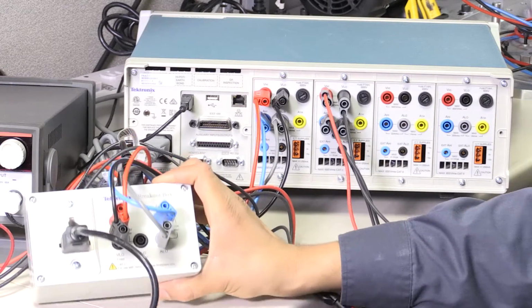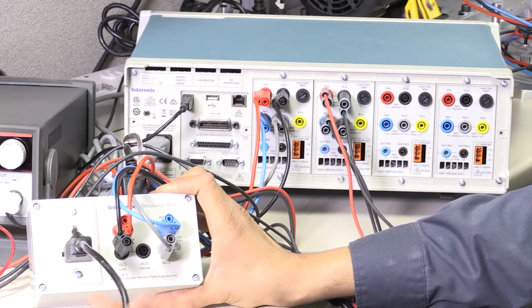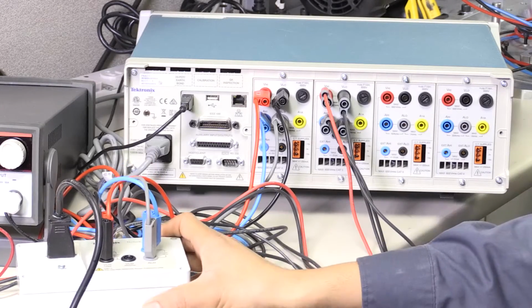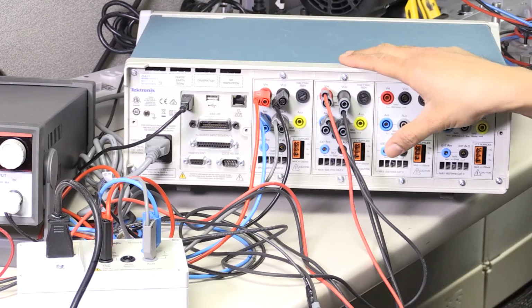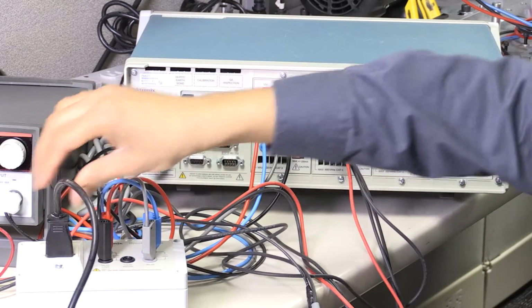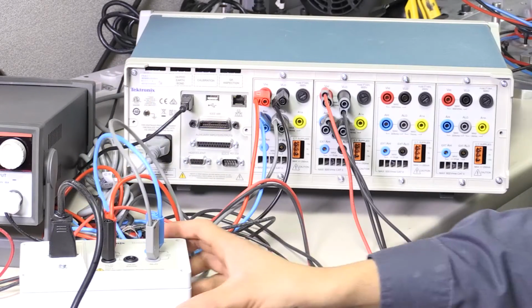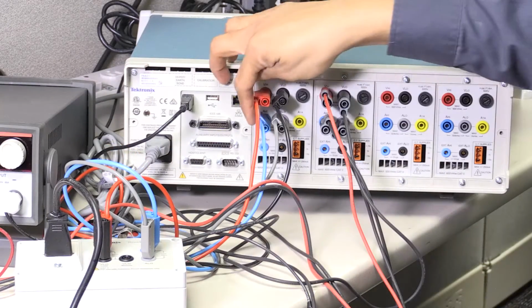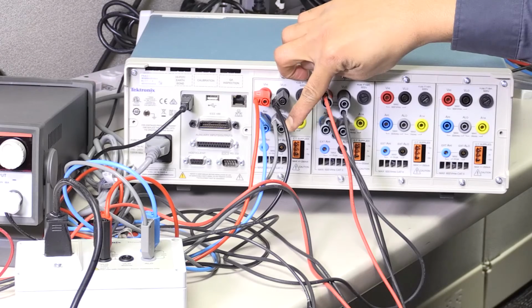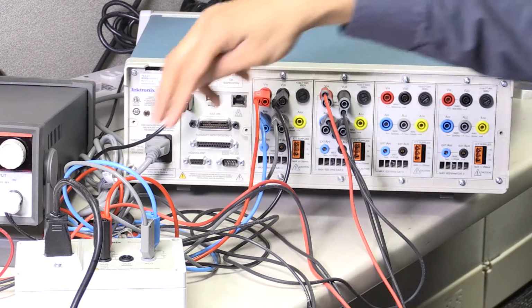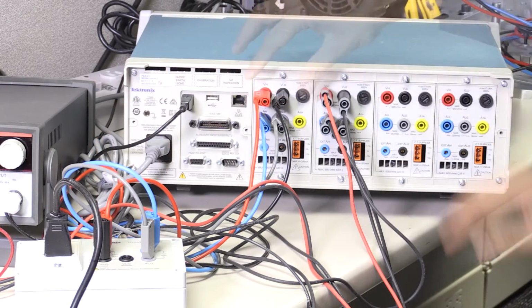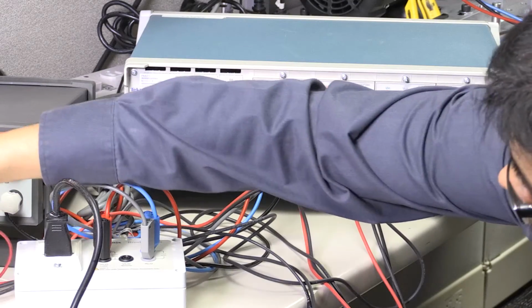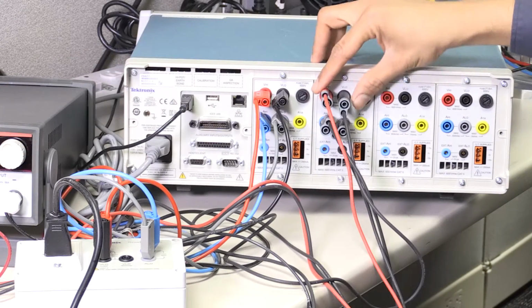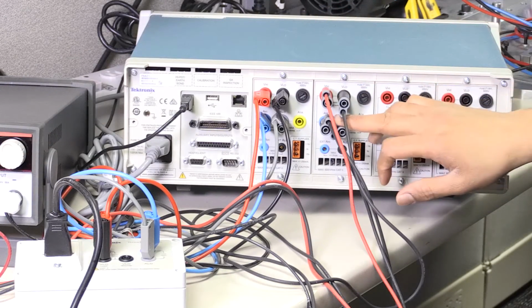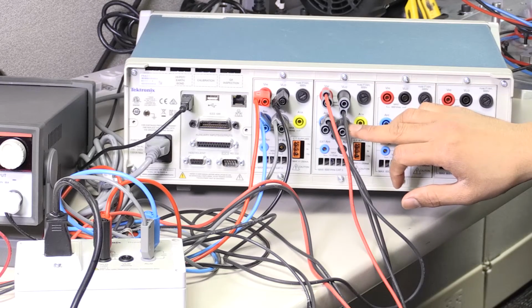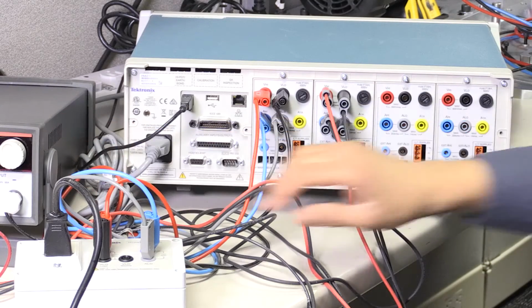We are using this breakout box to make the connections on the input side easy and safe. The breakout box will enable us to measure current flowing through the device by breaking the circuit and adding PA3000's internal shunt in series with it. We are also measuring the voltage across the input terminals. For the DC output, we'll have PA3000's channel 2 current shunt in series with the electronic load. We'll also measure the DC output voltage across the output terminals.